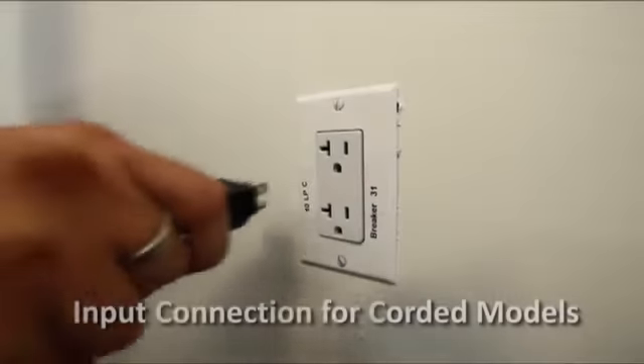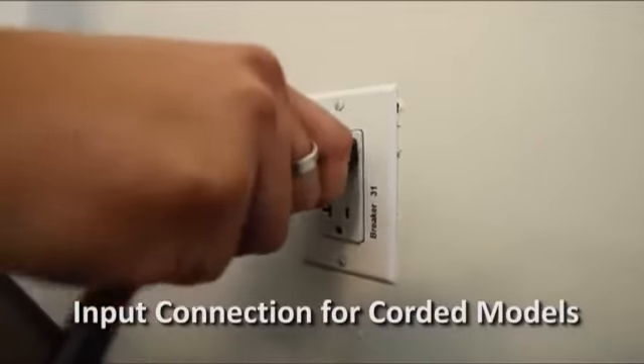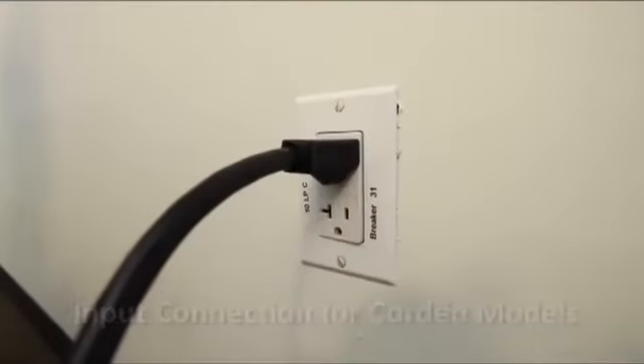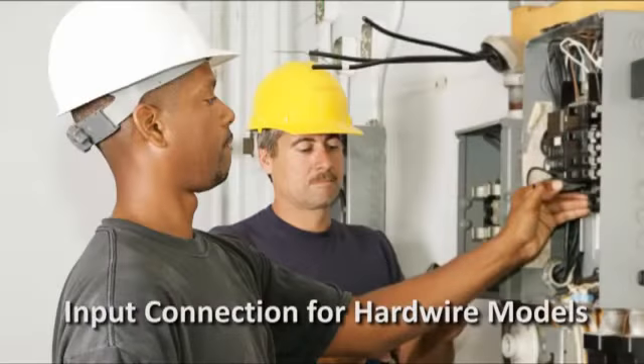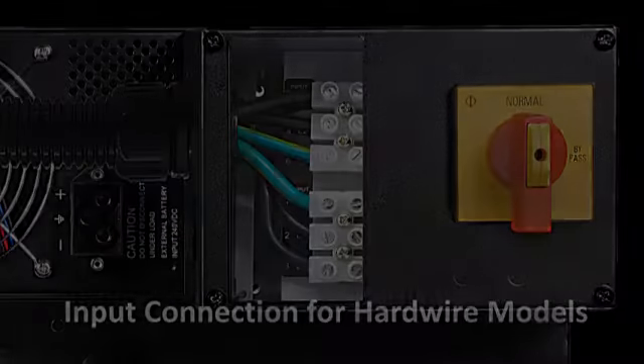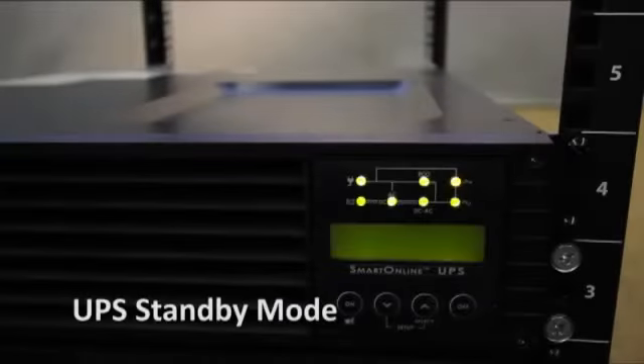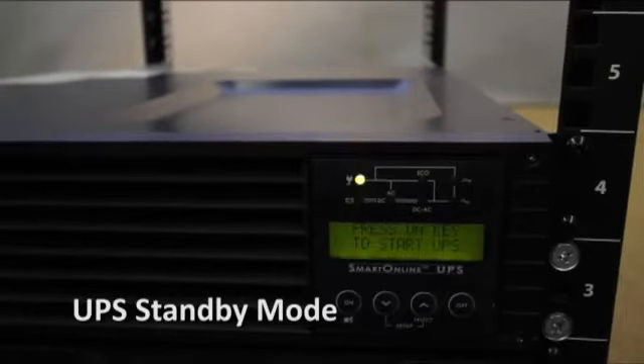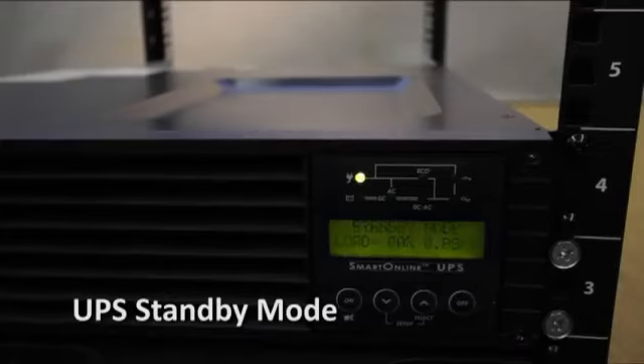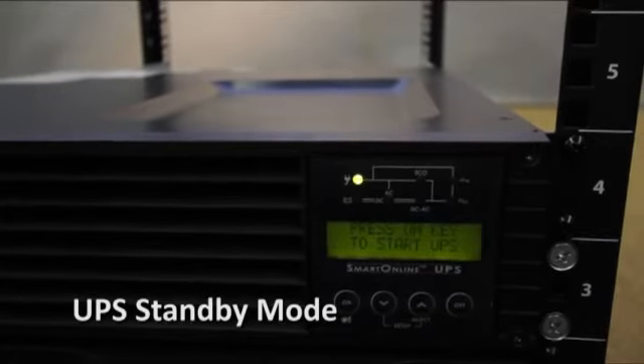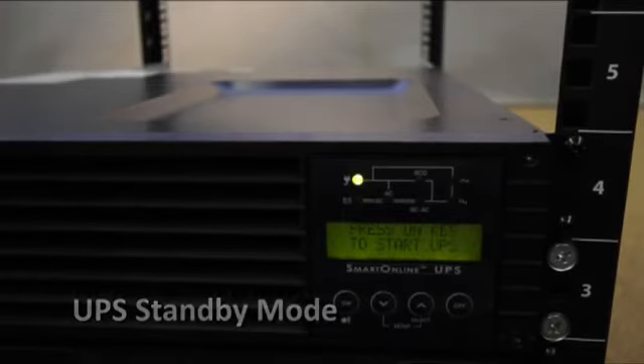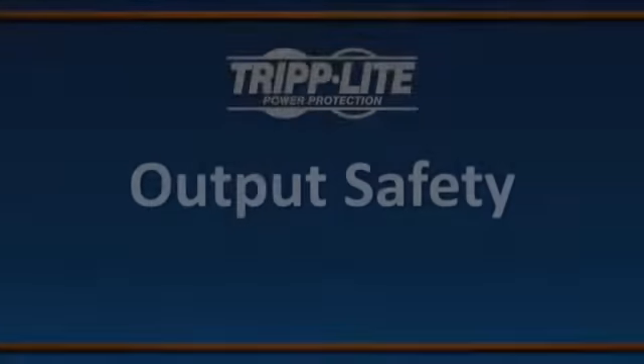For corded models, simply plug the UPS system's cord into a grounded wall outlet. For hardwire models, employ a qualified electrician to make connections following appropriate regulations. After connecting the UPS to a source of AC power, the UPS will enter standby mode. Fans and front panel indicators will be turned on, but power will not be supplied to the connected equipment until the UPS is turned on, which is covered in a separate video.